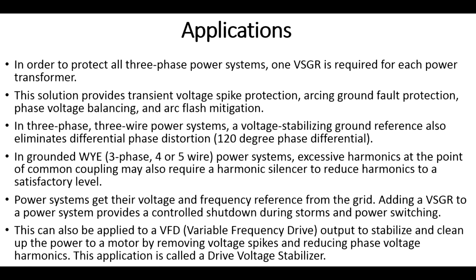The most noisy environment that I've ever detected is between a variable frequency drive and its motor. It has a very high magnitude of many different harmonics. It has a significant continuous pulse train of transient voltage spikes from the output switching transistors switching on and off. Many of these spikes can exceed 2,000 volts, which is why, for the power cable between the drive and motor at 600 volt rated insulation, there's a high failure rate. It is recommended by most manufacturers now to use 1,000 volt motor power cable. The IEEE for the marine industry has indicated you need to use 2,000 volt rated insulation to prevent the breakdown of the insulation due to these voltage spikes.